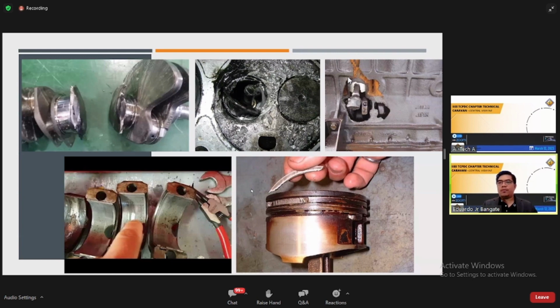For your information, based on my experience before, imagine you overhauled an 800 kVA generator, a big engine generator. And then after the overhaul and handover to the owner, within 3 days the generator broke, completely broke, and the engine was completely damaged. Like this. It can no longer be used. You can imagine the pressure, because we did not maintain our generators properly. It cost hundreds of thousands or millions because we had to replace it with a complete new set of generator for the customer. So that became a heavy problem. So always maintain your generators, both engine and alternator.